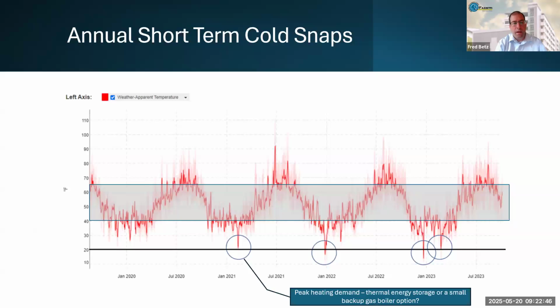So next slide, please. So as all studies should, we start with a climate analysis. Each facility is in a different location, therefore, by default, somewhat unique. And so the climate has an outsized impact on decarbonization. One, you see this gray band here, and it'll become more apparent what that is. That's the optimal operating zone for air source heat pumps. And then you see these 4 spikes, and this is actual meter data from the site through the BAS that shows what, in my experience, is somewhat unique, but it's unique to this part of the United States.